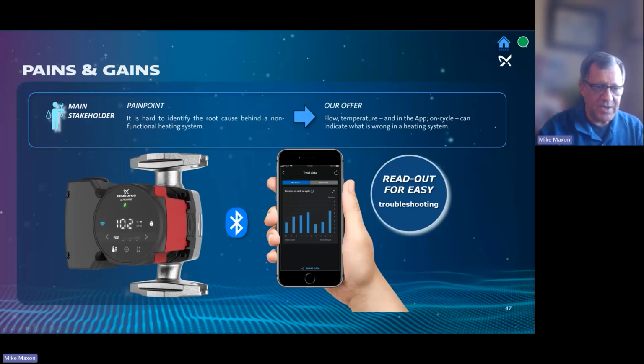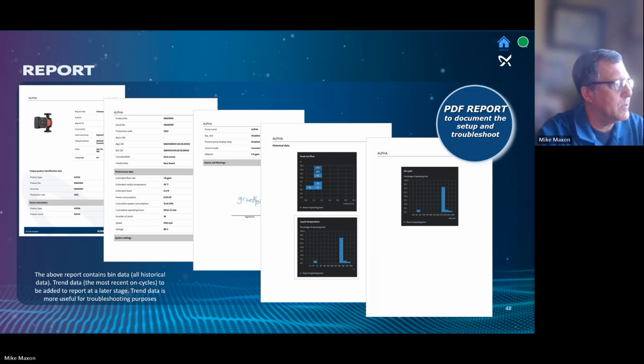So just like the heating product, we can get plenty of information on the faceplate of the pump, but we also have, through the Go app, all of the same trend data that we had on the heating pump. When the pump is set up, you could do a report. You create a report that'll tell you how you set it up, when you set it up, what pump it is, everything about that pump. Then you could email that report to yourself. This is the same for the heating as well as the HWR product.